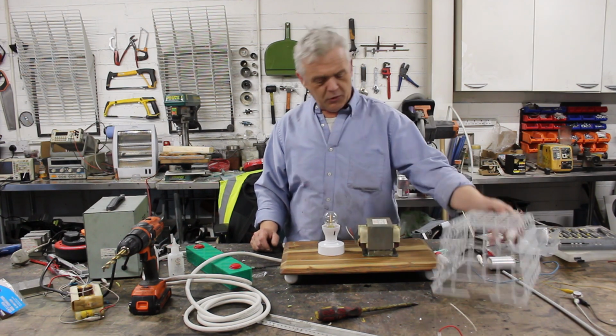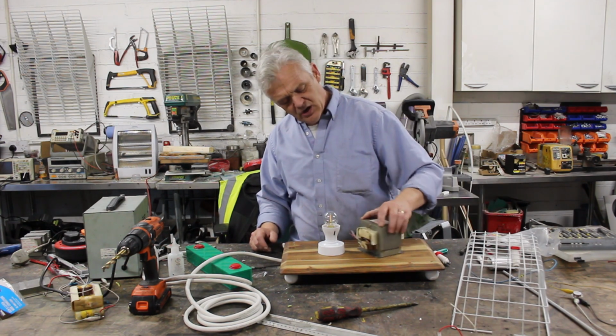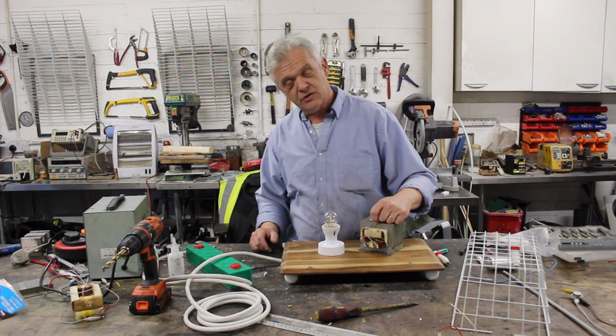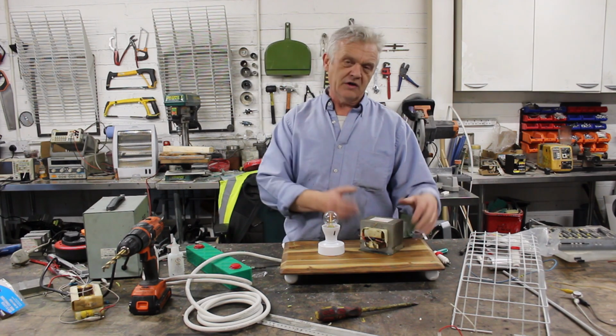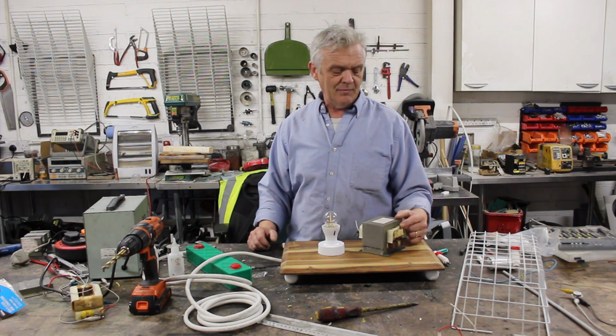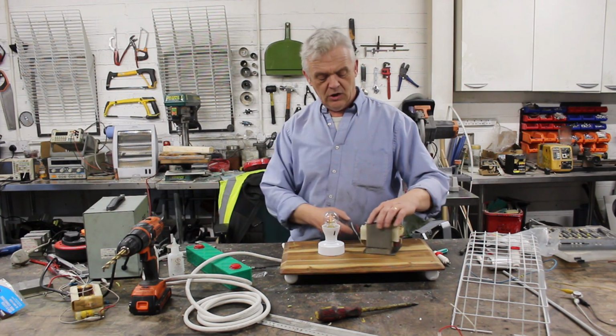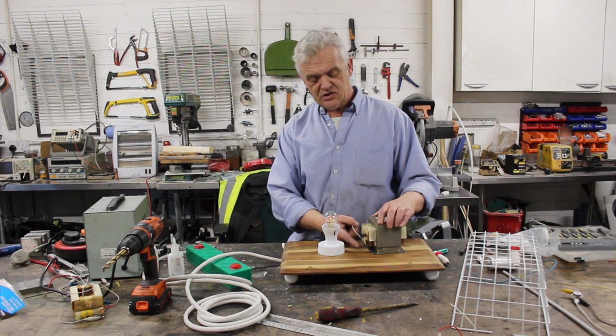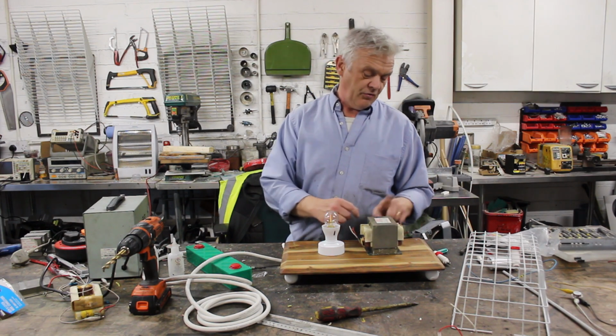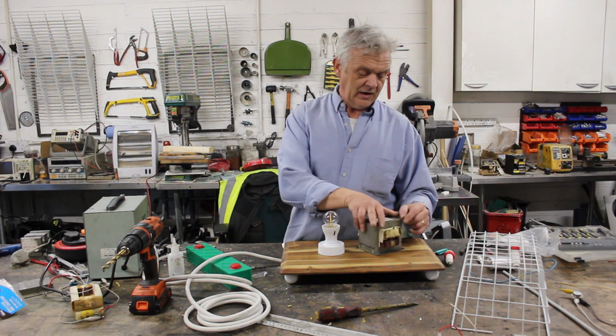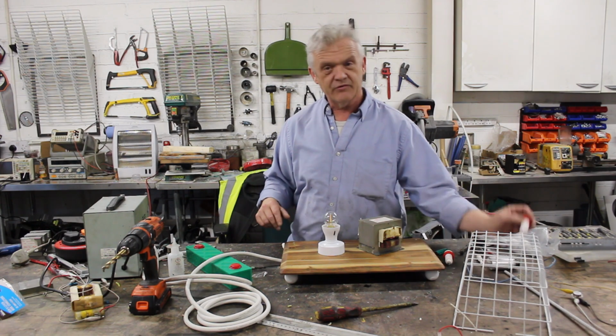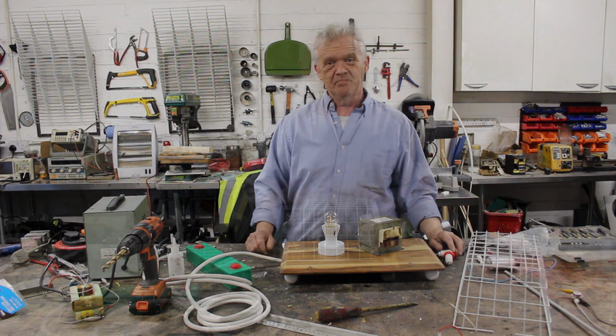There is one little point about this. This case here is where the return for the secondary comes in. So this whole block is actually your secondary return. That bit is your high voltage out. Those bits are your power. So we need to connect those to the lamp, and this to this, and this to the other one of those. So there it is, finished.